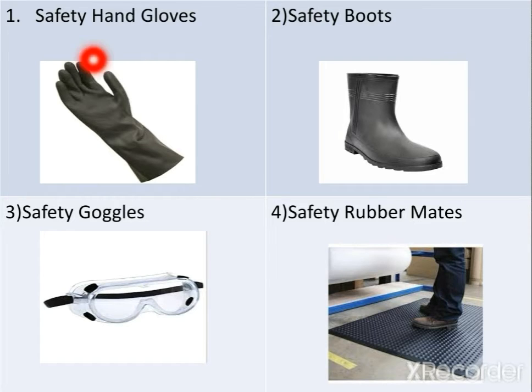Electrical gloves can protect the worker when the worker is working on the live circuit. The gloves of every employee must be sized. Gloves should be tested before their first use and after every 6 months. According to different voltage levels, the color of gloves can be decided. For example, for beige color, the maximum voltage of AC or DC system is 500 or 750 volts. For red color, it is 1000 to 1500, like that.